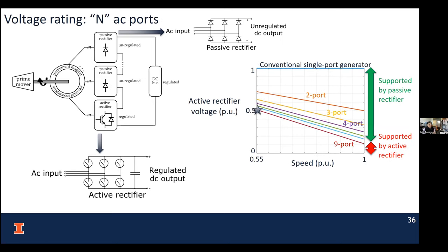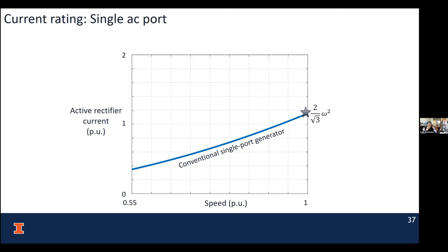So I can keep increasing the number of ports, and eventually you'll see we reach some kind of asymptotic behavior. As you increase the number of ports, the active rectifier voltage rating requirement, determined by the peak at the lowest speed, keeps going down. So it seems like the more ports, the better it is from a voltage rating perspective. Should we have an infinite number of ports ideally? But that's not true - why? Because there's another piece to the puzzle: the current rating of the active rectifier. If I take a single electrical port machine, the current rating is proportional to the square of the speed, as you can see.